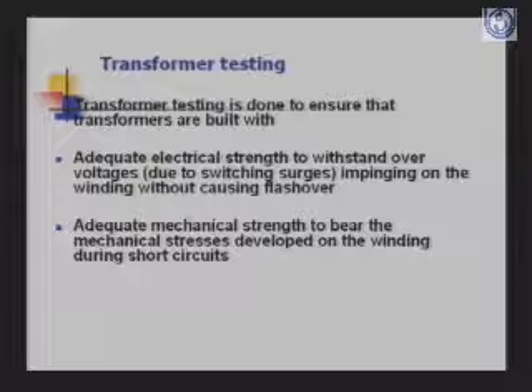Now we'll go to transformer testing. The transformer testing is done to ensure that transformers are built with adequate electrical strength to withstand overvoltages impinging on the winding without causing flashover, and adequate mechanical strength to bear the mechanical stresses developed on the winding during short circuits. The testing is done on the windings as well as on the insulating transformer oil before acceptance. Losses are tested before acceptance in routine tests as well as type tests and acceptance tests.